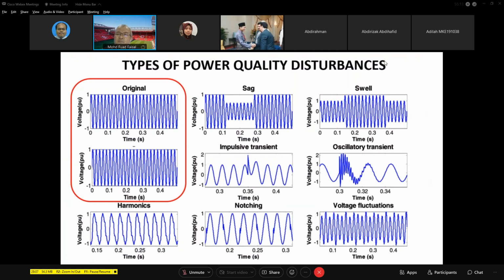So if the voltage waveform is perfect, we have normal power. If the waveform is reduced, we have under voltage. If the voltage increases, or reduces and increases, for more than 6 seconds, we have under voltage and over voltage. But if the voltage fluctuates, for example a voltage sag, it reduces slightly and goes back to normal. The same goes for voltage swell. If the voltage slightly increases, then goes back to normal. This is swell. As compared to over voltage, which will be permanent. As compared to under voltage, which will be permanent. For voltage sag, it's only a short duration.